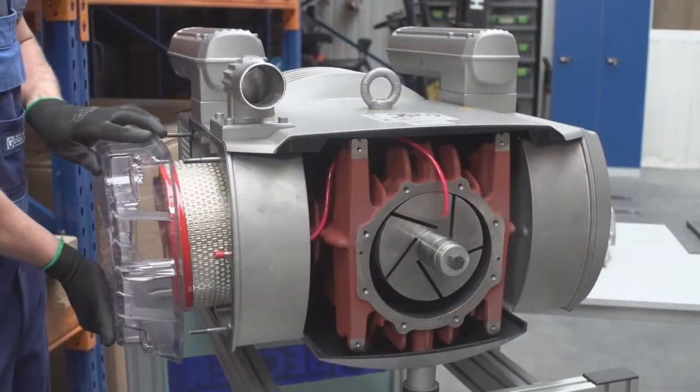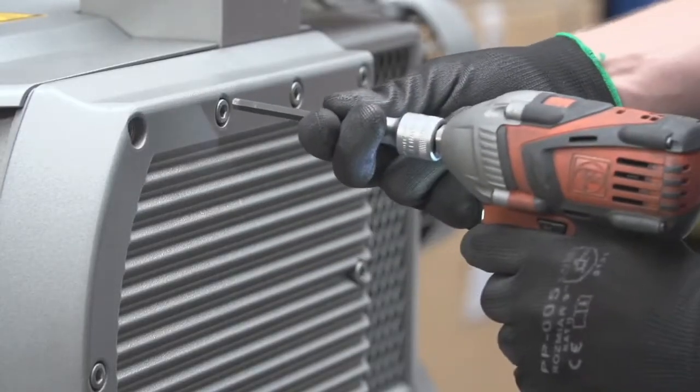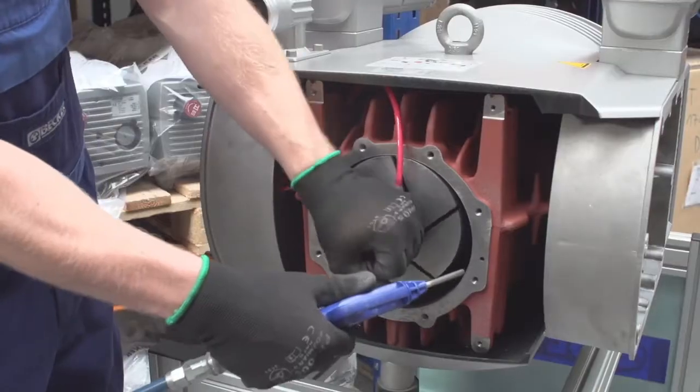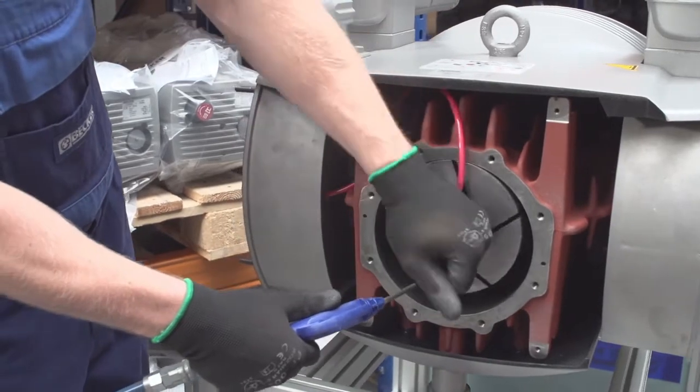In order to remove any vane dust, remove the covers. Blow out the suction chamber, exhaust port, and intake port. Then blow out the cylinder while rotating the rotor.